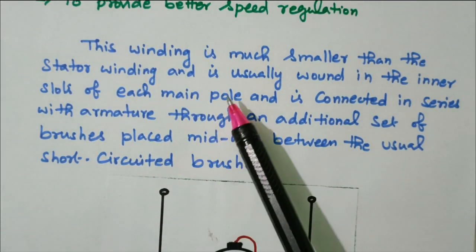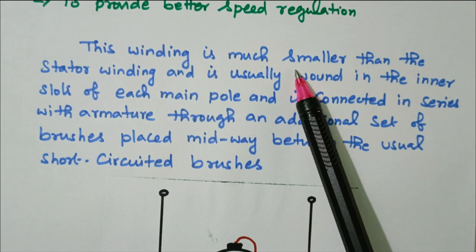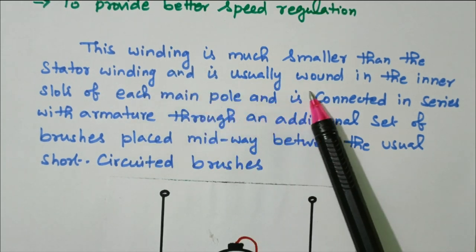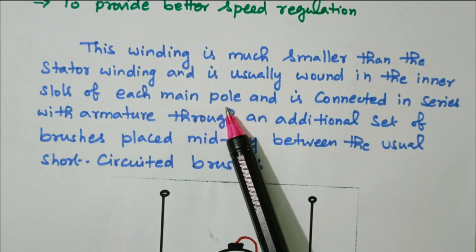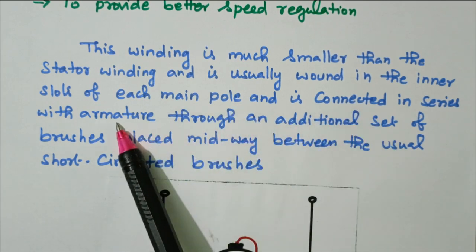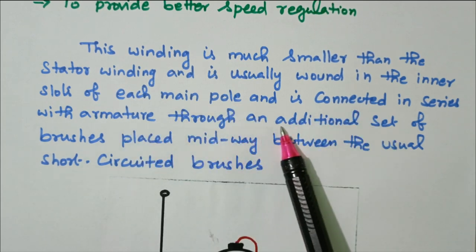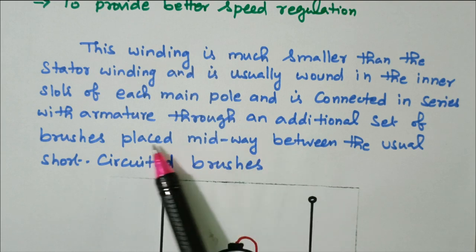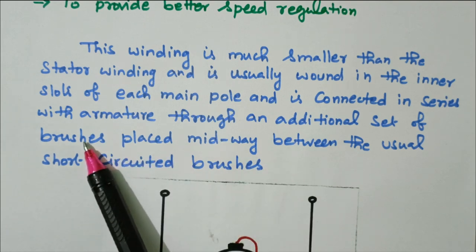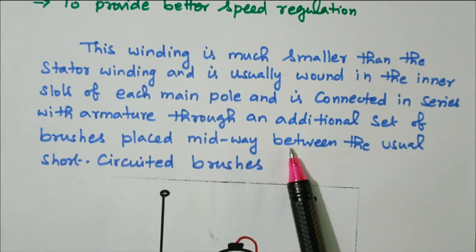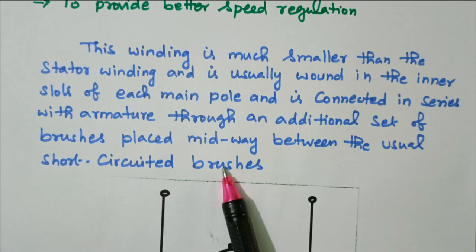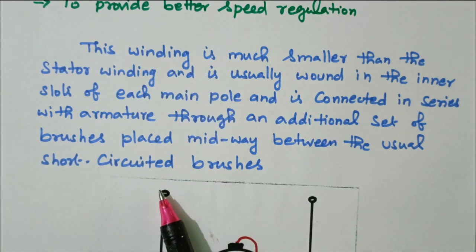This compensating winding is much smaller than the stator winding and is usually wound in the inner slot of the main poles. It is connected in series with the armature through an additional set of brushes. Already two sets of brushes are present, and this compensating winding is placed midway between the usual short-circuited brushes.